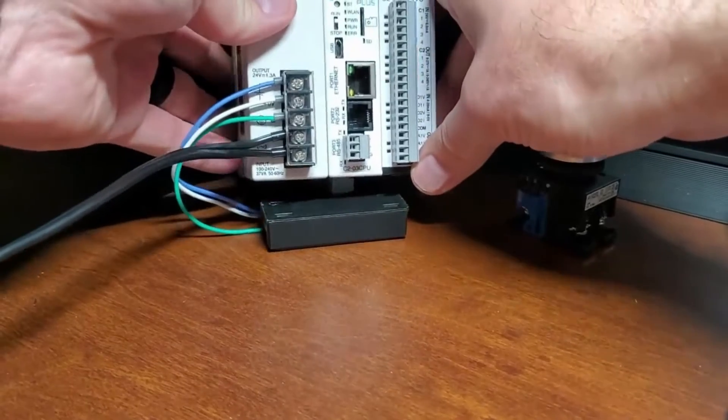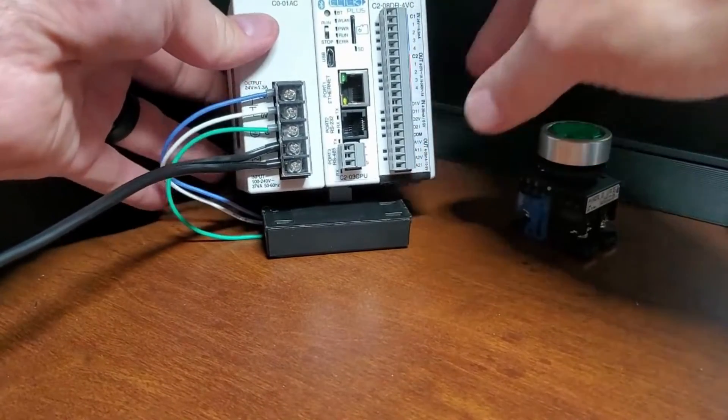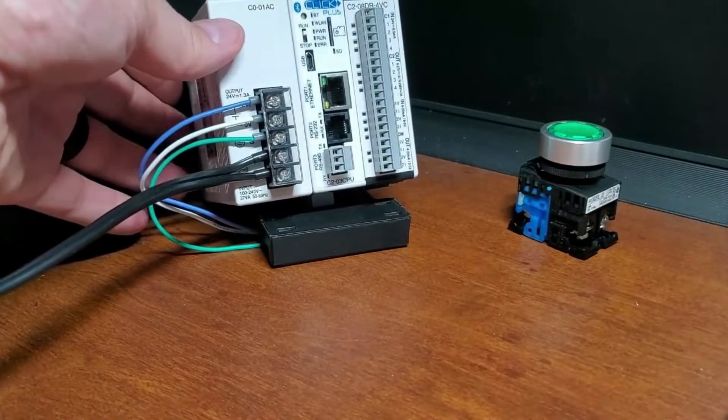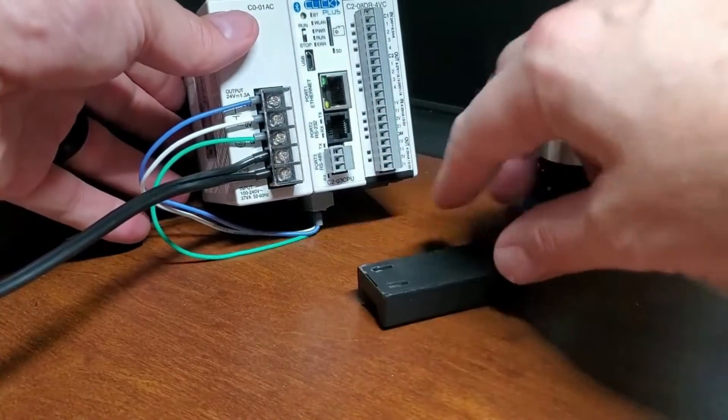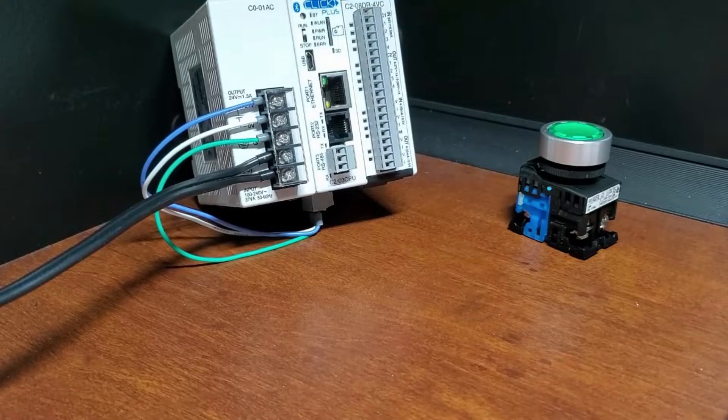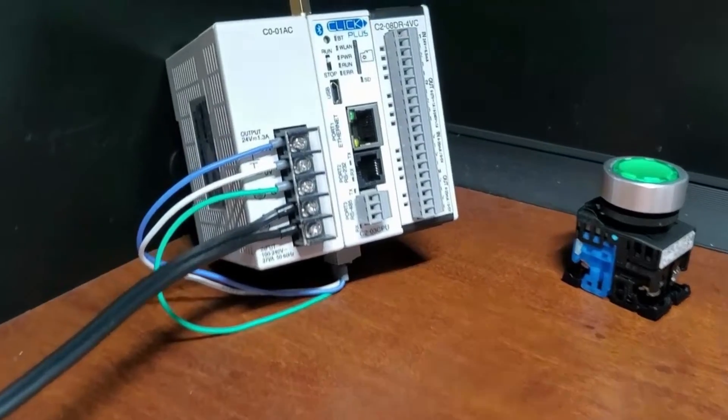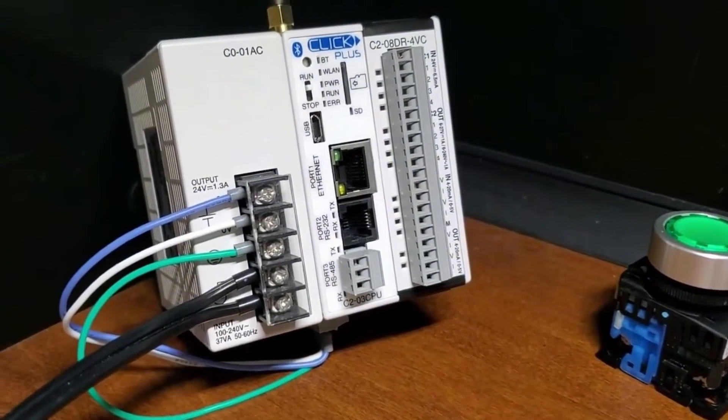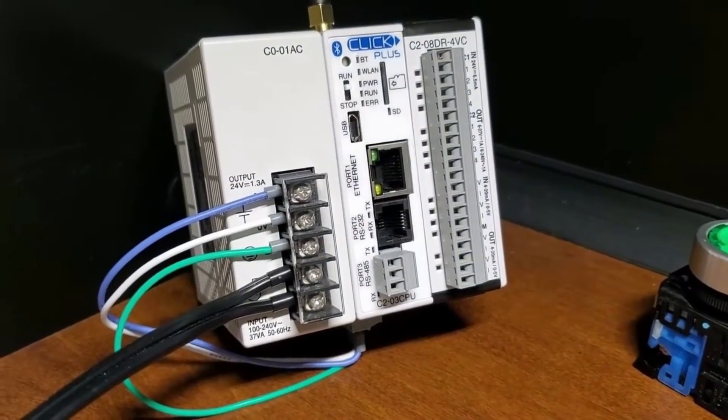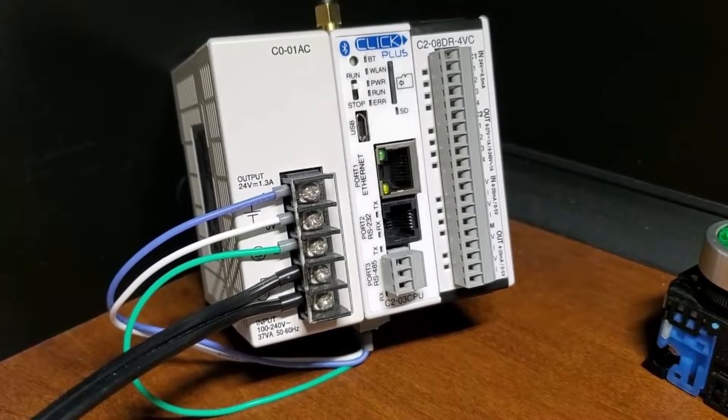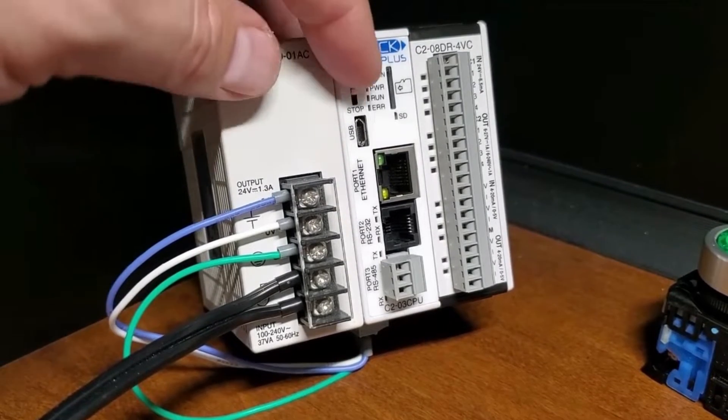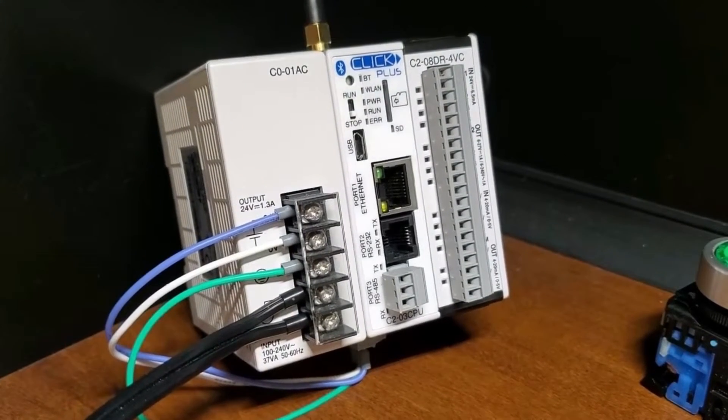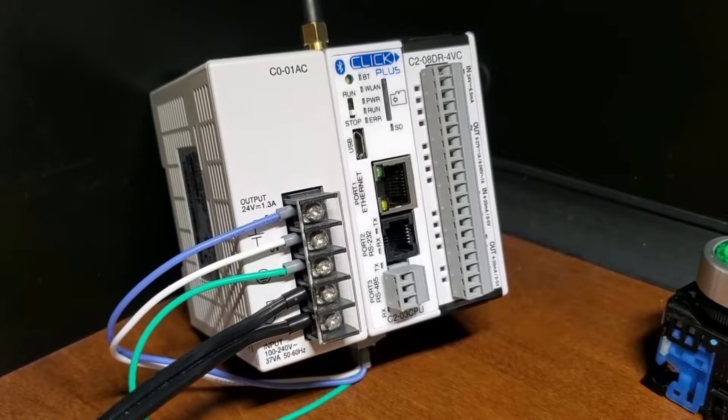24V DC power is supplied to the CPU unit through a wiring connection from the power supply output to the 4-pin input connector on the bottom of the CPU unit. The 24V DC, 0V DC, and ground are wired from the power supply to this connector.